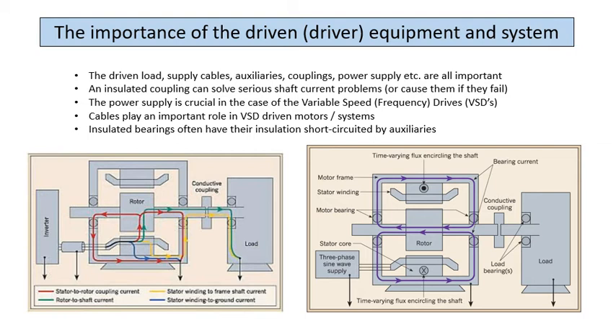Okay, the driven equipment, and I'll show you an oscilloscope trace later. If you have a common mode voltage and you've got both bearings insulated, but your load is earthed, you're going to have a lot of current going through your load. If you've got electrostatic voltage being generated by your load, or if your load has had welding done on it, because you're far more likely to weld on your mechanical driven equipment than on your electrical rotating machine, it can also pump current back into the system.